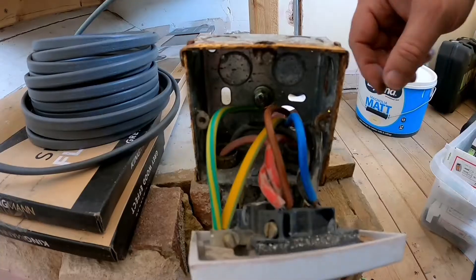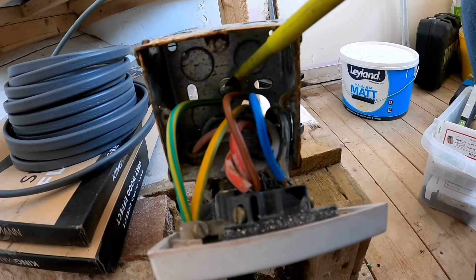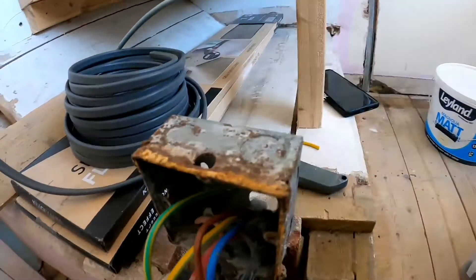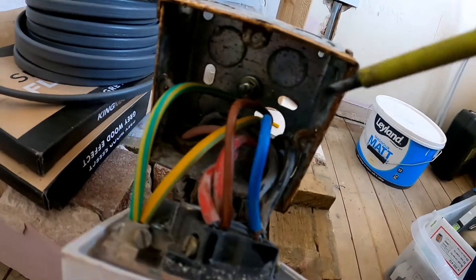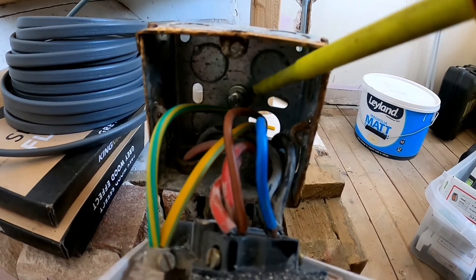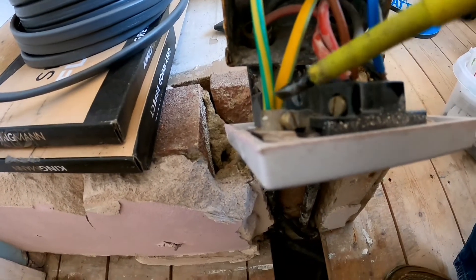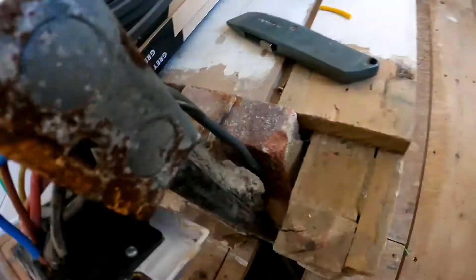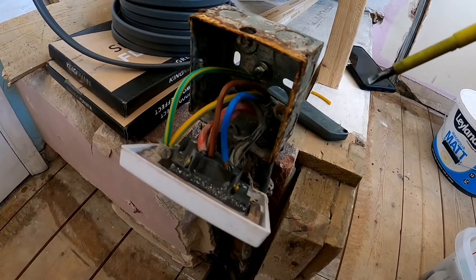As you can see, what I've done is put my nut and bolt here, tied this cable in, wrapped it around the back, and tightened that bolt up at the back of the unit — just with the nut. There's a compression washer on here to make sure it stays tight, and a normal washer so it holds flat against the back as it's compressed. I've run that wire into the earth, which goes out the back and down the cable off to my Wago box, which is now living under the floor.